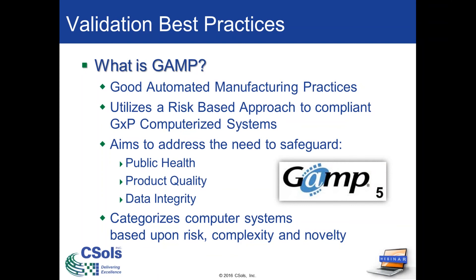The most current version is referred to as GAMP 5, and it lays out the foundation for achieving compliance and fitness for intended use for all GXP-regulated systems in a pragmatic and efficient manner. Many corporations leverage the outlined practices in GAMP 5 while validating complex computer systems, such as Empower III, because GAMP 5 categorizes computer systems based upon risk, complexity, and novelty. GAMP 5 categorization then outlines a specific risk-based approach to validating such categorized systems.